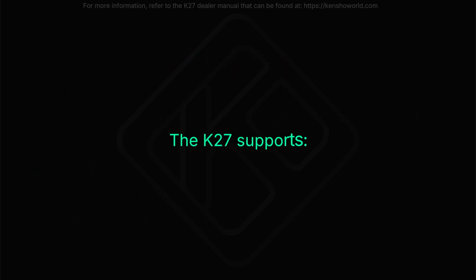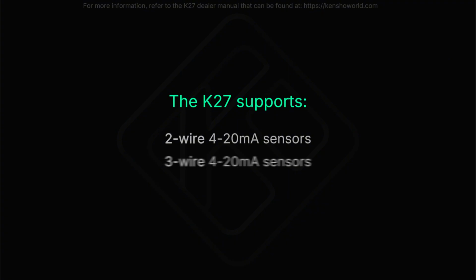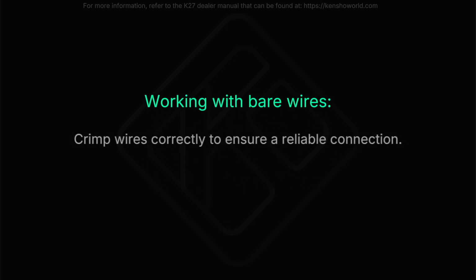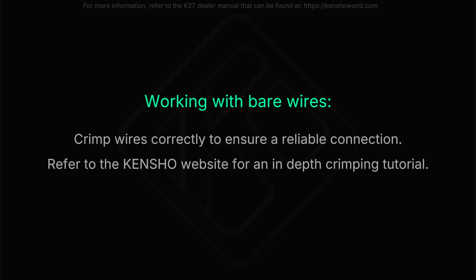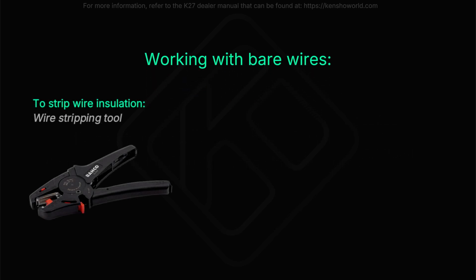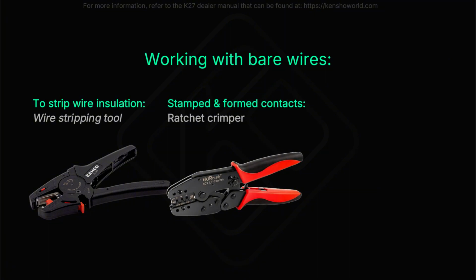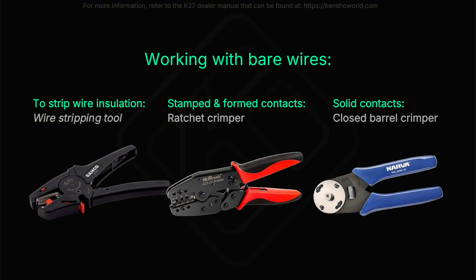The K27 supports 2-wire and 3-wire 4 to 20 mA sensors, with a range of up to 1,000 liters per second. If your sensor was supplied with bare wires, it is important that you are crimping your wires correctly to ensure a reliable connection. Refer to the Kensho website for more information on wire crimping. Be sure that you are using the appropriate tools for the task. Refer to the tools shown for reference.